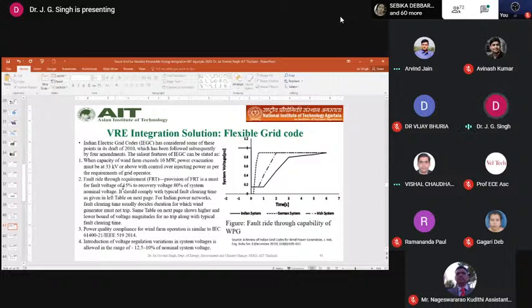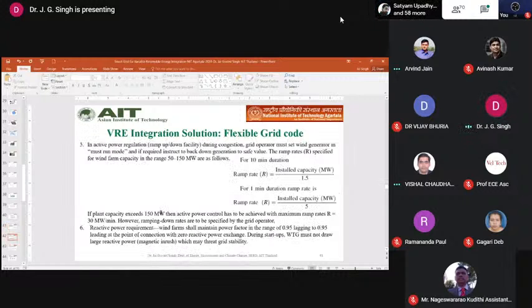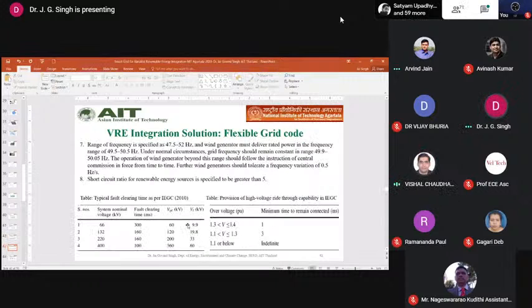And the FRT requirement is, for a fault voltage of 15% to a recovery voltage of 80%, meaning it does not allow 0%, 15% is the minimum. And the clearing time is given in the next table. So these are the additional things you can see here. This table says, if this is the nominal voltage and this is the PF.